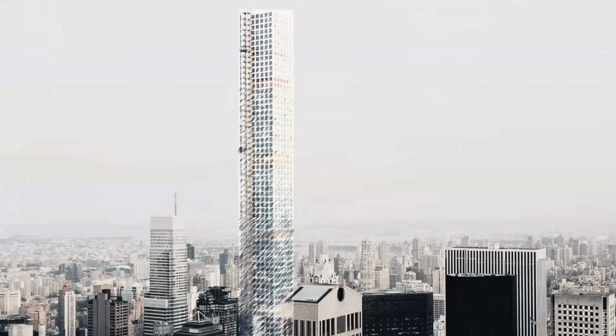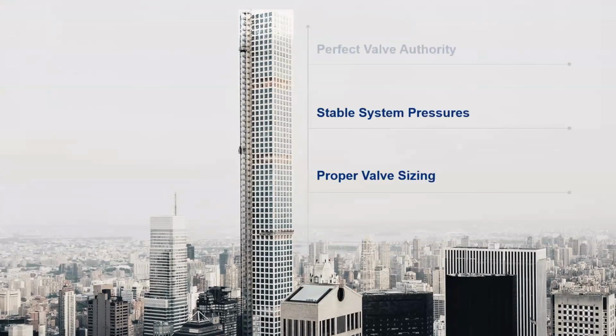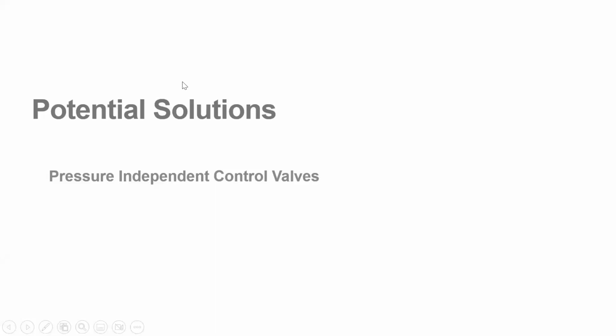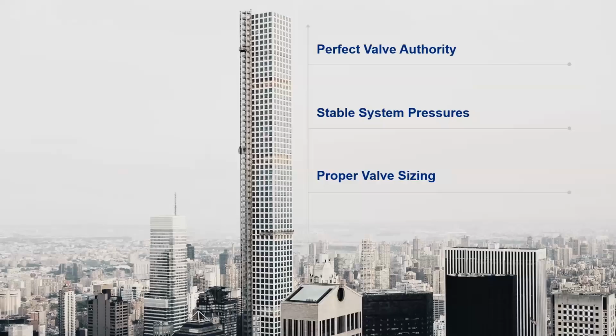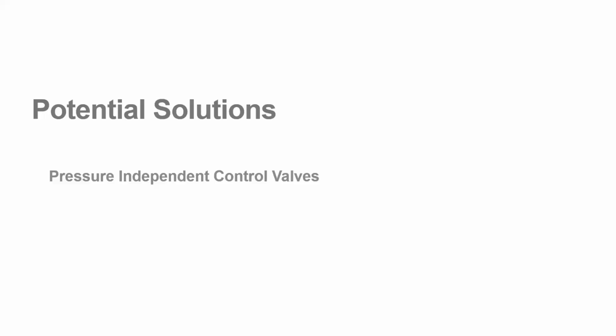So remember, this is what we're modeling. So what can we put in a building to actually work like this? Again, we went through proper valve sizing, we went through perfect valve authority, and we went through stable system pressures. And we discussed how none of those are true in most applications. But we can look at a potential solution of pressure-independent control valves.